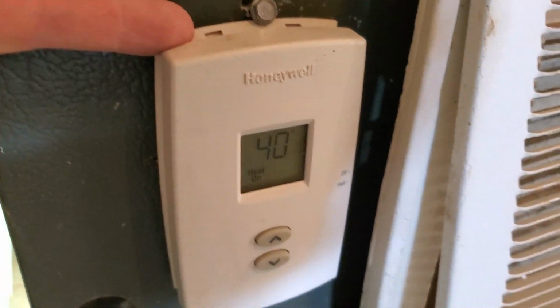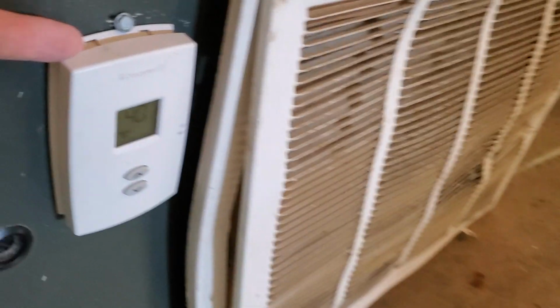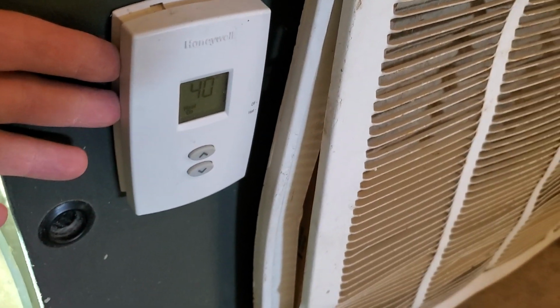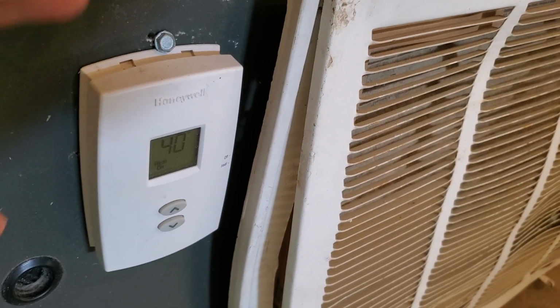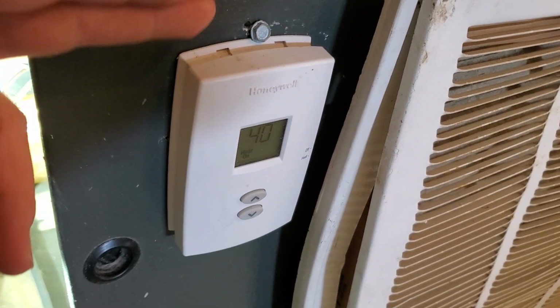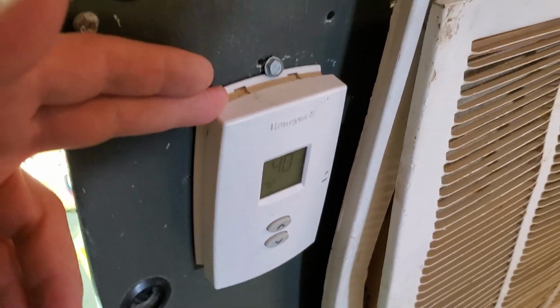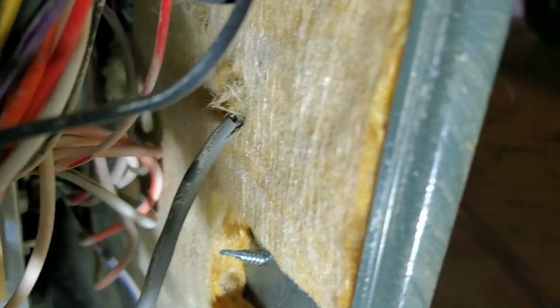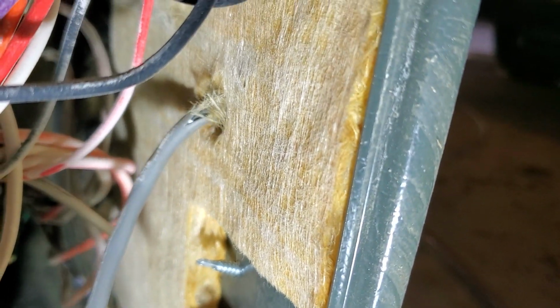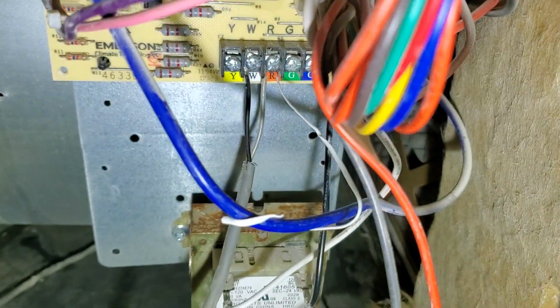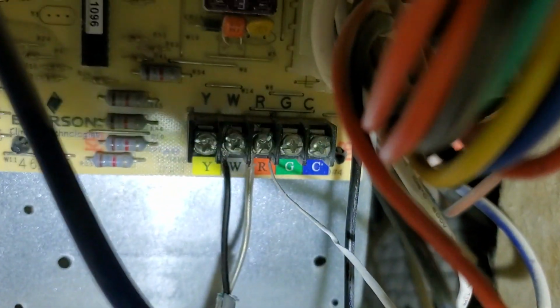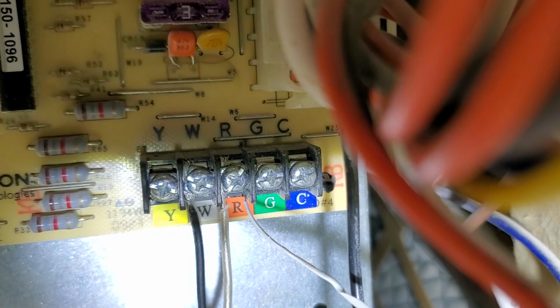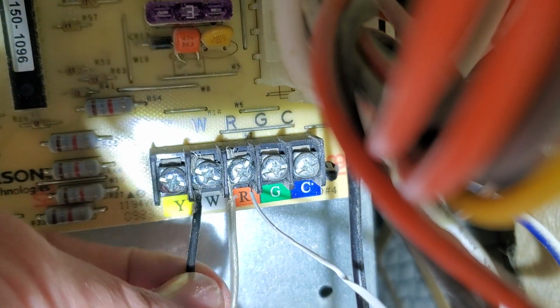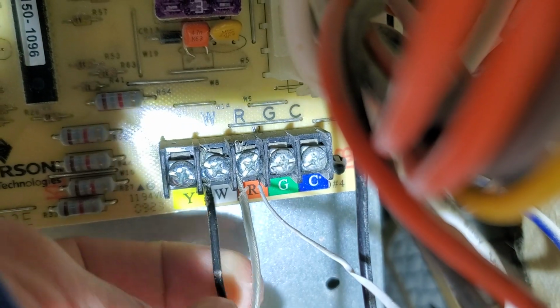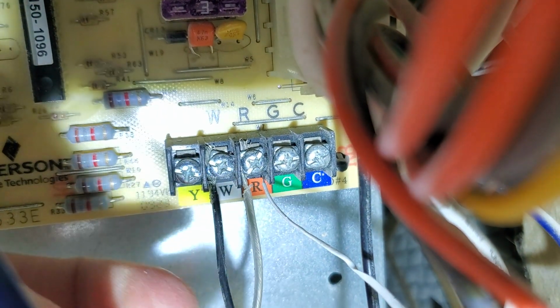Now you obviously need something to control the furnace. In this case we have a little digital thermostat that's just mounted out here near the return air. Now this isn't optimal. It might cycle a little bit faster than we want it to, but it works good enough for what we need it for. This is just a heating only thermostat, so I'll show you the way it's hooked up inside of here. We have just this wire here that's going to that thermostat coming through the sidewall, and then it just comes down, hooks onto the control board. And you can see right there, we just have it hooked to the R and the W. So R right here and W right next to it. When you cross those two, that will start the furnace.